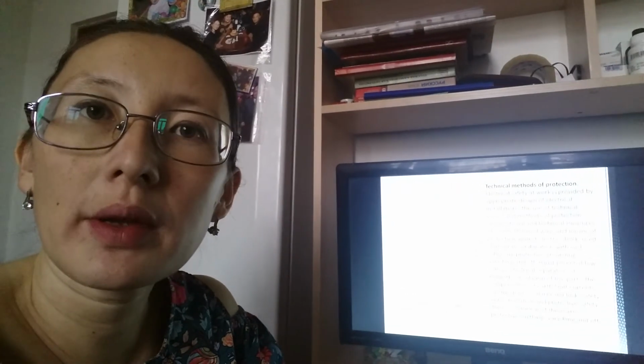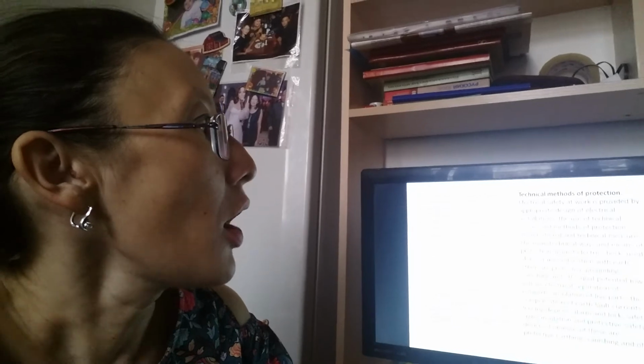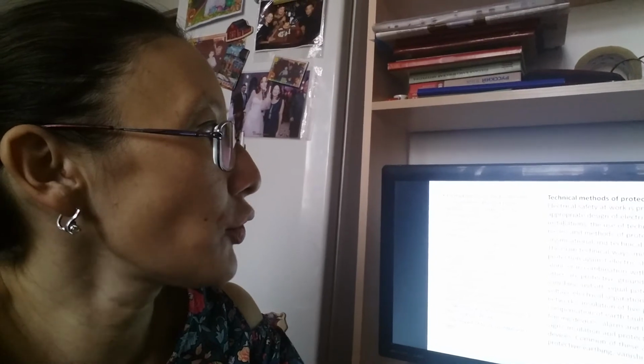Earth neutral, what does it mean? Earth neutral is a generator or transformer neutral attached to the earthing system, either directly or through a small resistance. Next, isolated neutral. It's the neutral of a transformer or generator not attached to the grounding device, or connected to it through devices such as alarm, metering, protection, grounding and supervision, reactors and the like, with a lot of resistance.